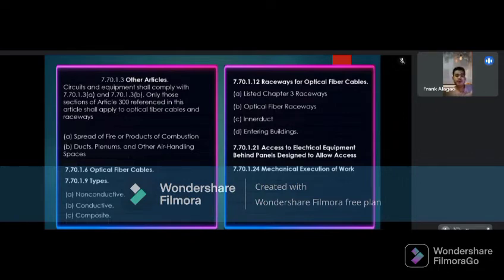B is yung optical fiber raceways. Optical fiber raceways for listed optical fiber cable shall be permitted to be installed in listed plenum optical fiber raceway, listed riser optical fiber raceway, or listed general purpose optical fiber raceway. So letter C is yung innerduct. Listed plenum optical fiber raceway, listed riser optical fiber raceway, or listed general purpose optical fiber raceway installed in accordance with 7.7.3 shall be permitted to be installed in innerduct in any type of listed raceway permitted in Chapter 3.